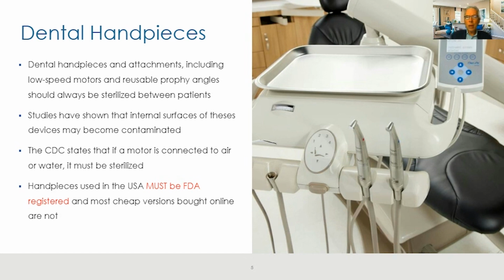But one thing people sometimes don't realize is that we also have to sterilize low-speed motors. The reason is studies have shown that the internal surfaces can become contaminated through this Venturi effect. It literally can suck bacteria and virus into there, then spit it back out through a sterile contra angle. So what the CDC states is this: if a motor is connected to air or water, it needs to be sterilized. Simple as that.